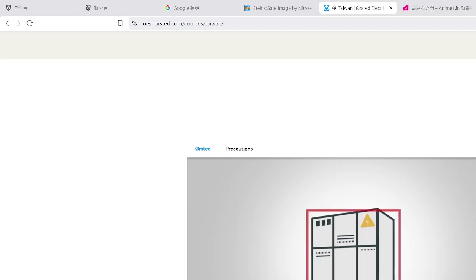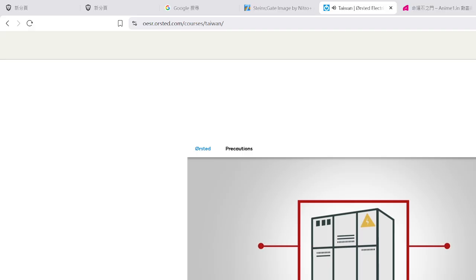The next step is to isolate equipment from all sources that may make it energised, and to establish points of isolation. When isolating devices are used, they must, where practicable, be immobilised and locked. Prohibition signs must be affixed to all isolation points. When the work involves high voltage equipment, primary earths must also be applied, and, where reasonably practicable, immobilised and locked. The primary earths must be marked with prohibition signs, and the earths must be recorded. If necessary, drain earths must be applied to prevent danger. Any additional precautions to achieve safety from the system during work on equipment must be specified in the safety document.